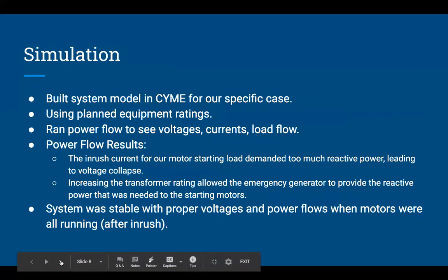To simulate our resilience zone, we built a model in CYME. We used the planned equipment ratings, and we ran power flows to see voltages, currents, and load flow. From the simulation, we saw that the original equipment parameters were not sufficient, and we saw voltage collapse due to motors starting demanding too much reactive power. We tried to increase the generator sizing, but that didn't resolve the issue. But increasing the transformer sizing allowed more reactive power to flow through, and we verified that the system was stable with proper voltages and power flows when all the motors were running.